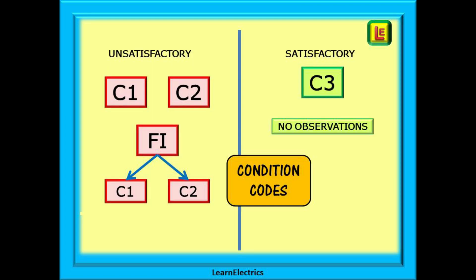Any C1 or C2 code will automatically deem the installation unsatisfactory, as will an FI, or further investigation code, as this may lead to a C1 or a C2. Only C3s or no observations at all will allow us to class the installation as satisfactory. An unsatisfactory installation can continue in use at the customer's risk — not the inspector's — if the customer takes appropriate steps to control the risk until the problem is repaired or dealt with. Such repairs must be carried out in a timely fashion.